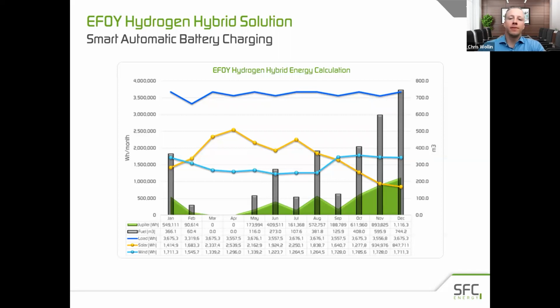The fuel cell itself monitors the battery voltage and sits in standby mode until there's insufficient input from the solar and or wind, and the battery voltage drops to the switch on threshold. At that point, the fuel cell would turn itself on, provide supplementary power as required before going back into standby mode once the solar and wind is sufficient again to maintain the batteries.